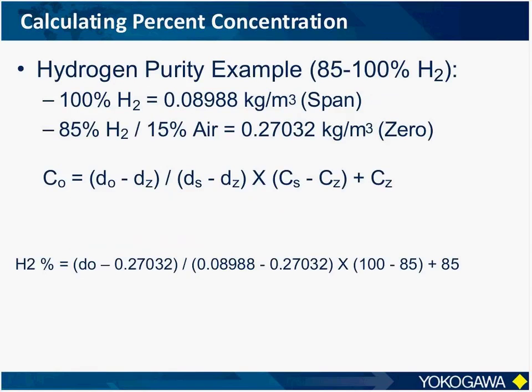Now, as an example, if we want to measure the purity of hydrogen in the range of 85 to 100% in air, we know the densities associated with the span and zero concentrations. We simply program these constants into the analyzer. The analyzer measures the density of the process stream, and based on that density, it calculates the percent concentration of hydrogen.